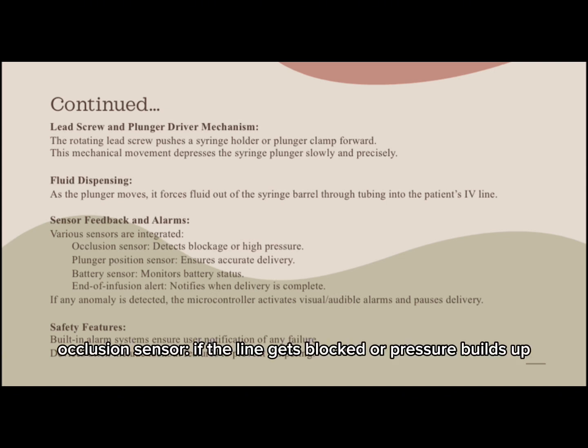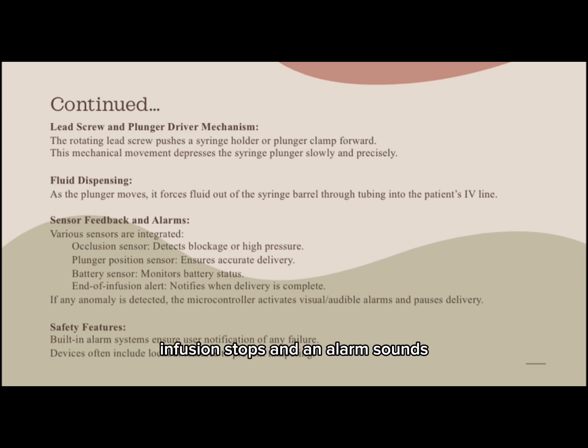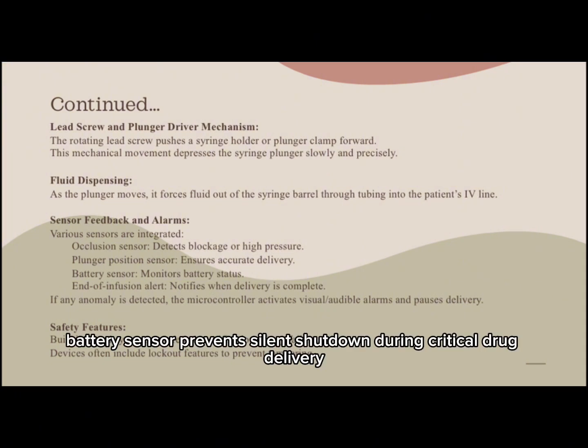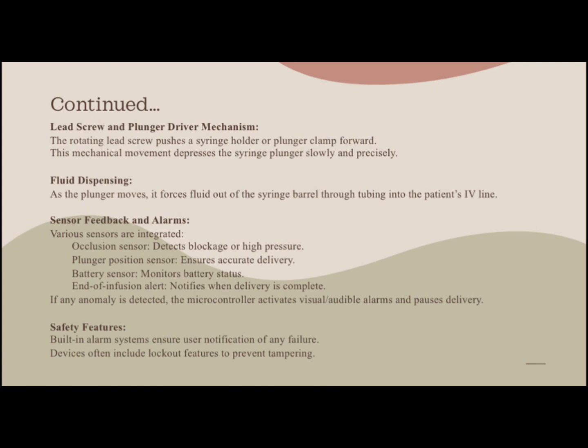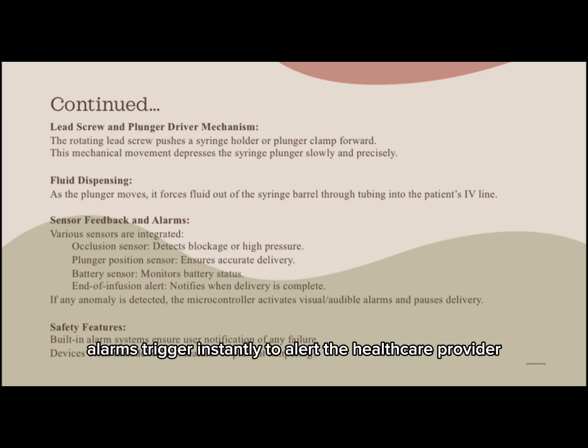Occlusion sensor: if the line gets blocked or pressure builds up, infusion stops and an alarm sounds. Plunger position sensor ensures the infusion matches the planned delivery rate. Battery sensor prevents silent shutdown during critical drug delivery. If any error like tubing kink, battery low, or syringe empty happens, alarms trigger instantly to alert the healthcare provider.